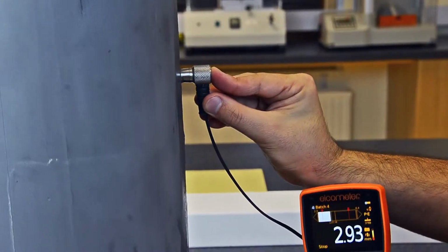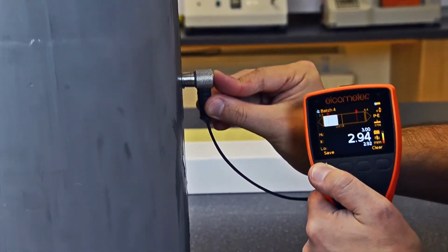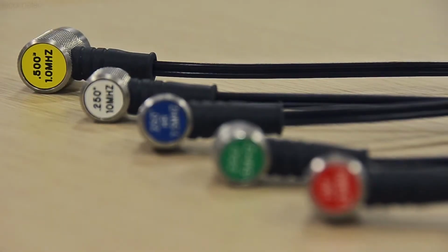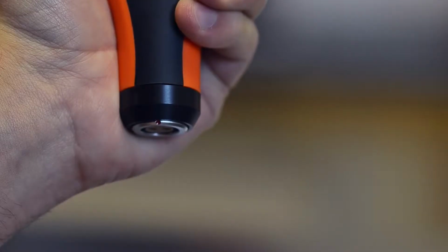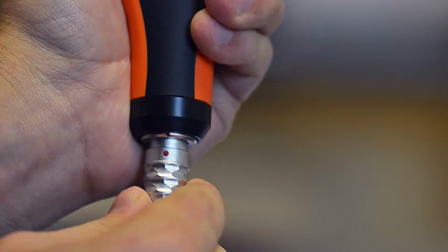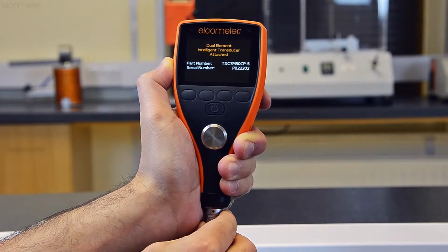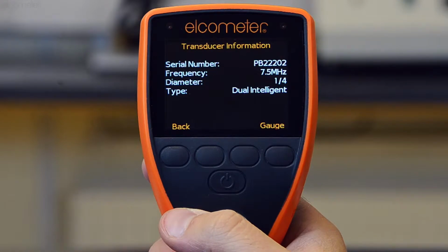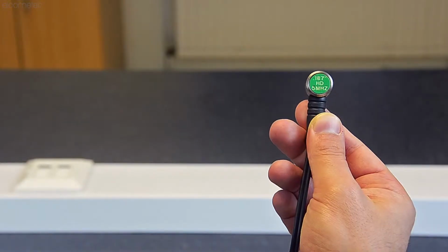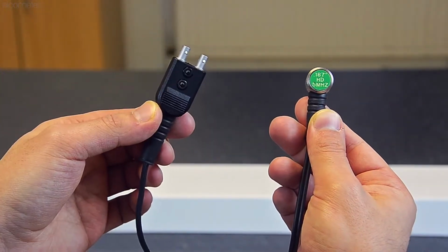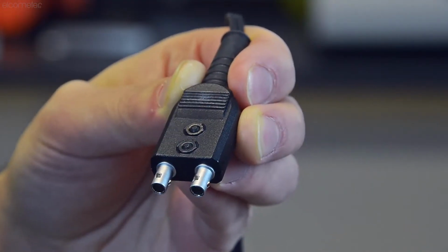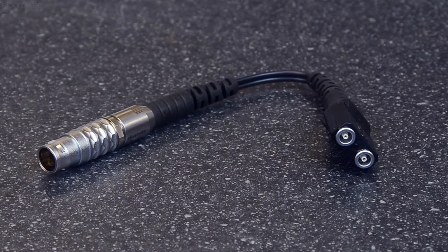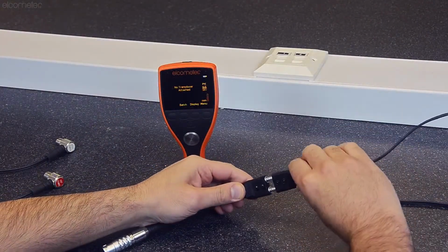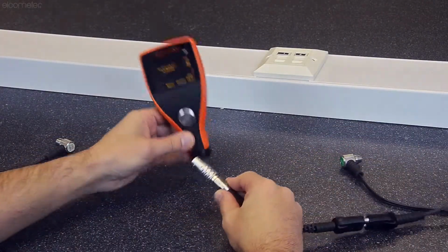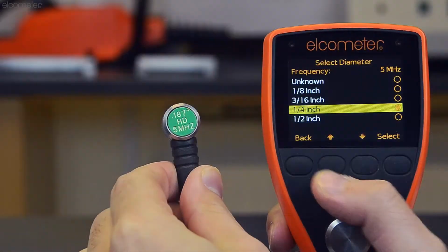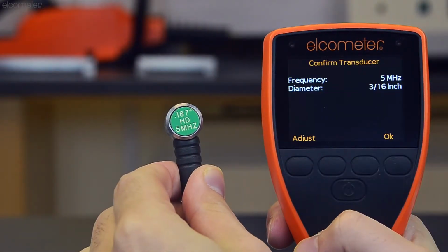The Elcometer 304 and Elcometer 307 thickness gauges are designed to work with Elcometer's range of intelligent transducers, which all have automatic probe recognition. So as soon as the transducer is connected to a gauge, the gauge immediately detects what type of transducer you're working with. If you already have a range of transducers you wish to use, which have LEMO connectors, they can be connected to the Elcometer 304 and Elcometer 307 gauges using a single or dual element transducer adapter. All you have to do is tell the gauge what transducer you're using.